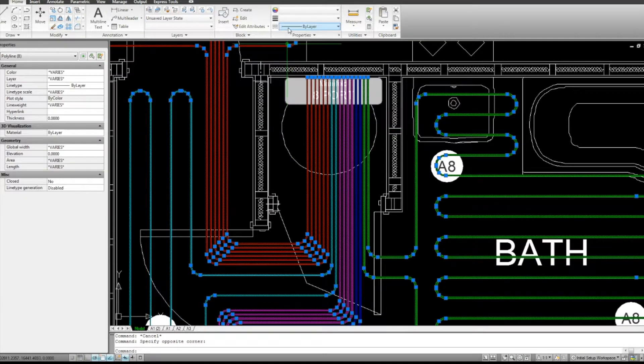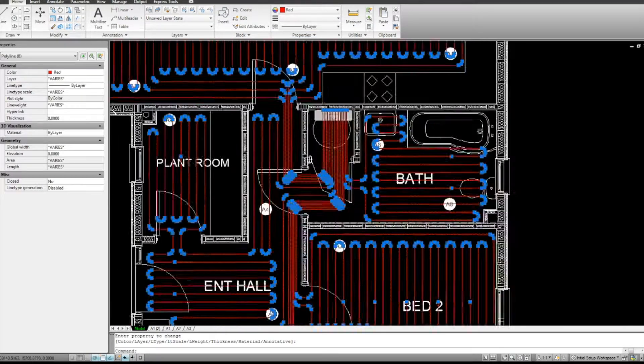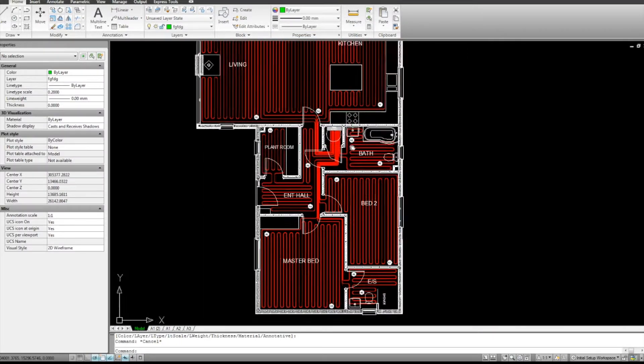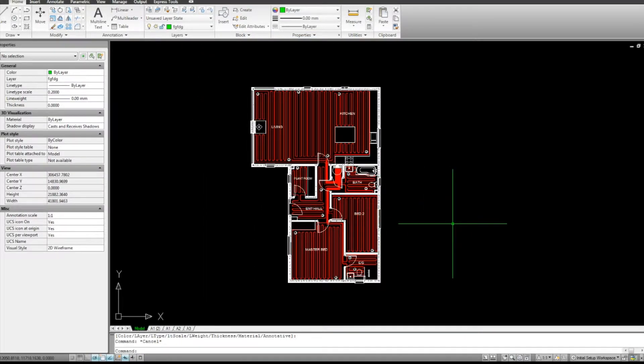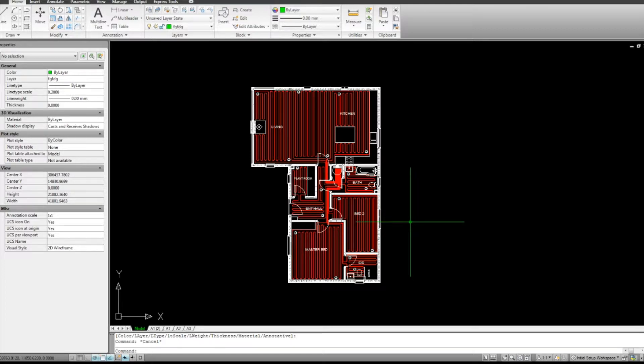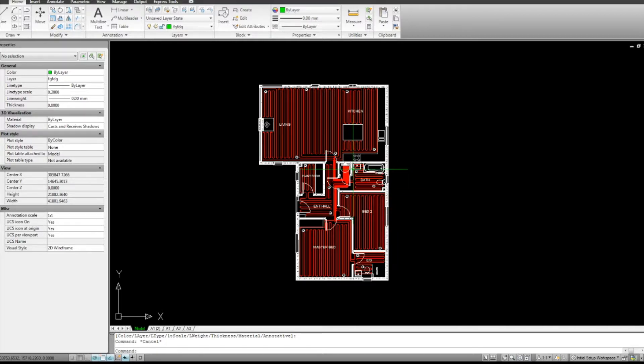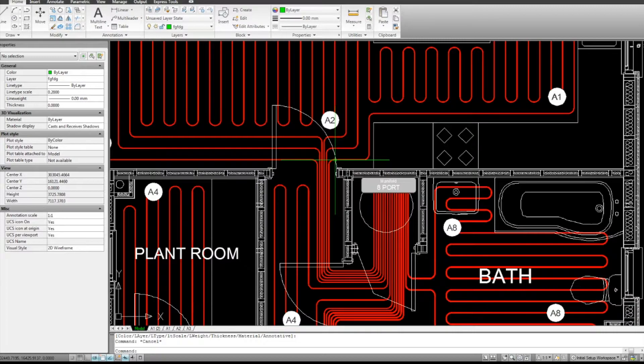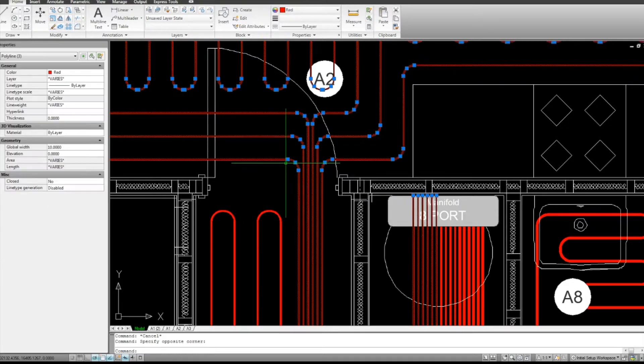On the other hand, what we could do is have one thermostat in the house, one zone, and that's all you have. Now the location of that thermostat would be a little more tricky because it needs to take an average temperature throughout the whole house. So that's the good thing with underfloor heating. You could have as many or as little thermostatic zones as you want.